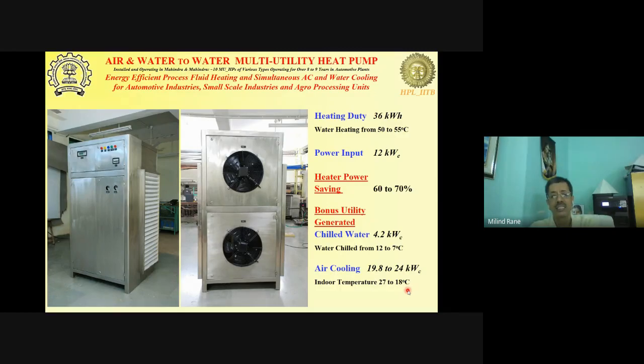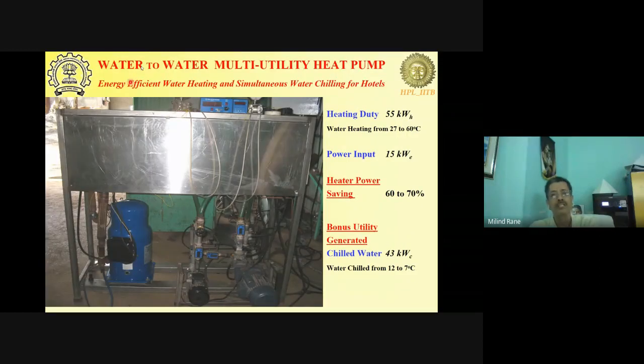So as I said, in this case, we are taking the air from both sides, it gets filtered, goes through the evaporator coils placed behind it, and then these fans return it back into the room. And while this is happening, the hot water is recovered from the condenser side. And chilled water also, there's an additional heat exchanger inside which produces chilled water. So this is a water-to-water heat pump. That was an air-water-to-water. Heat was taken from air, part of it from water, and then delivered to water. In this case, it is just water to water.